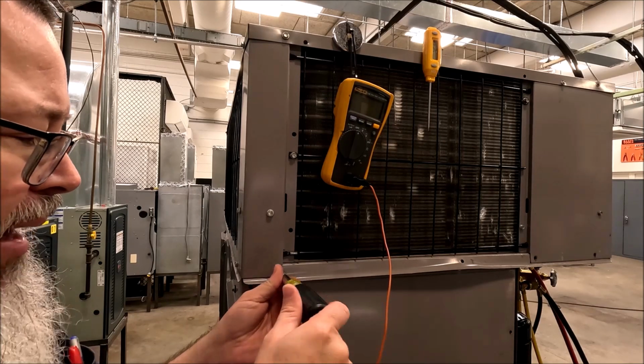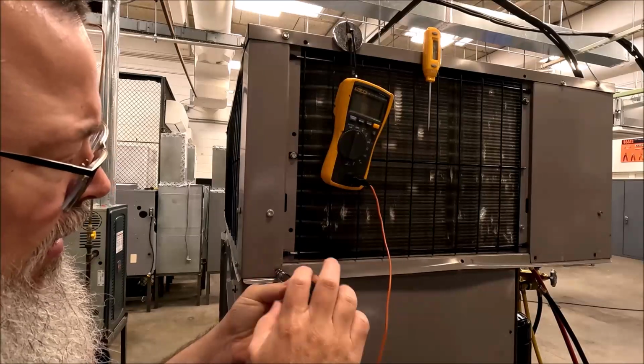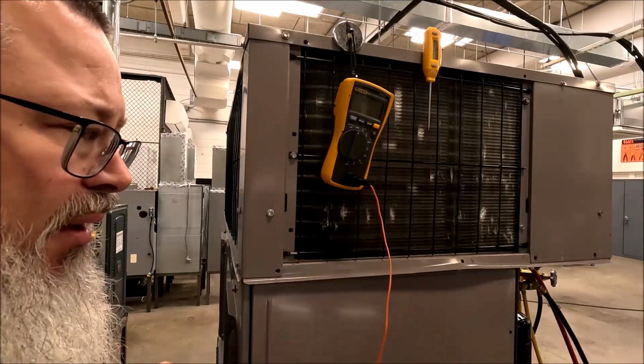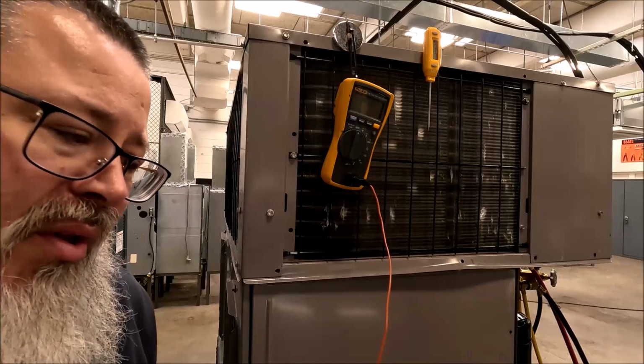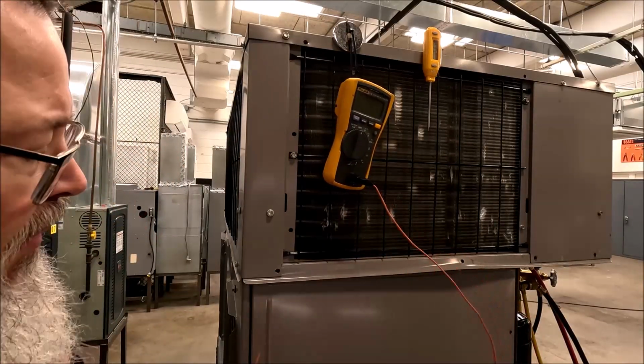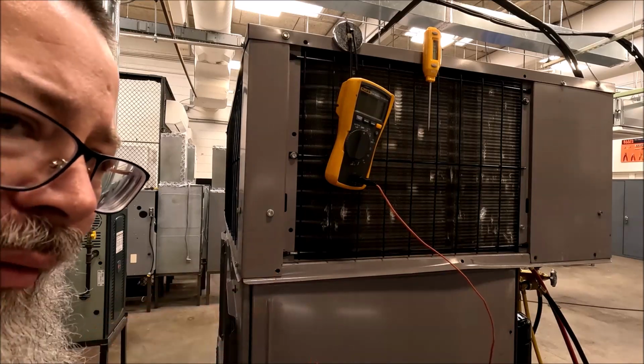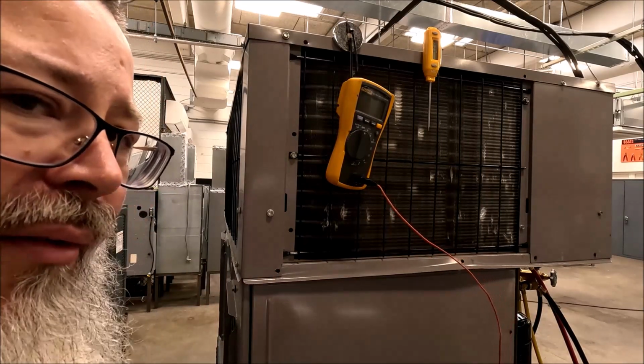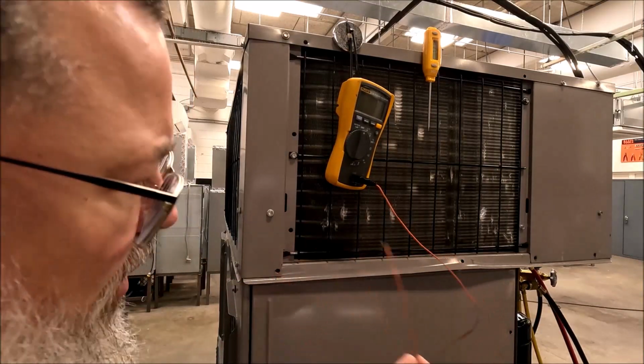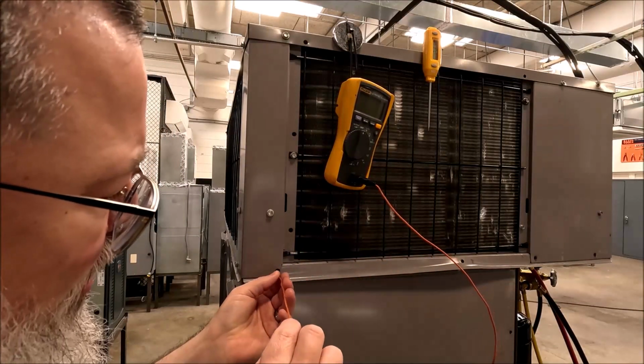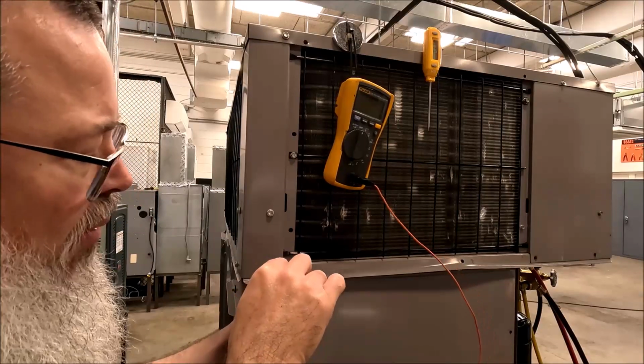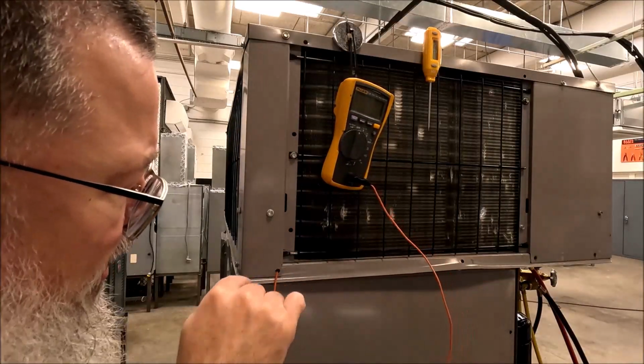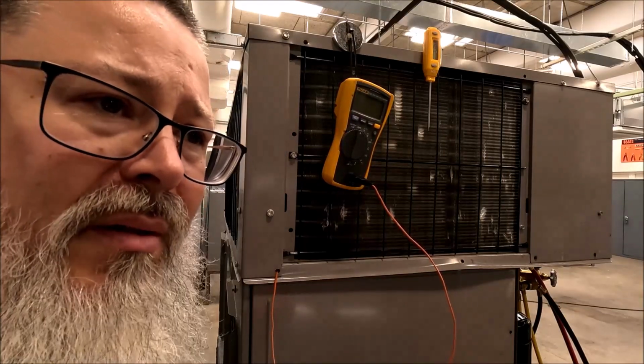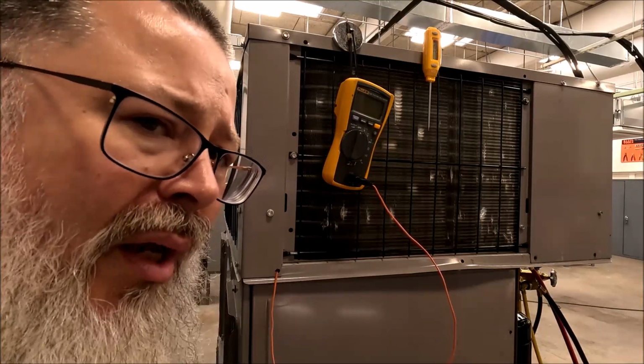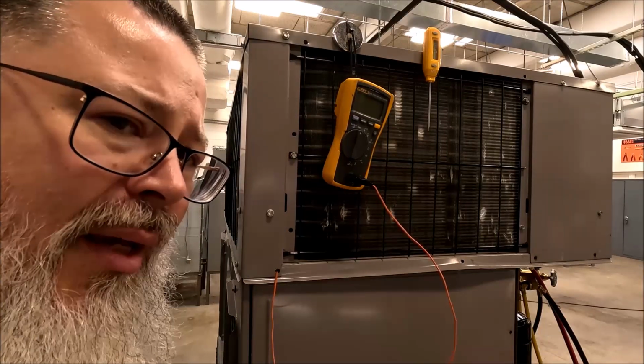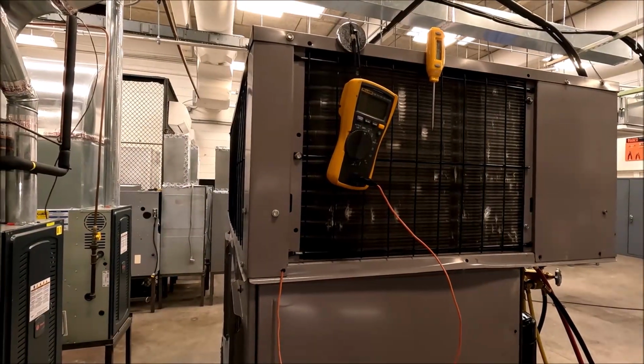And then what I would do is take one screw out. I've seen guys drill holes in the side here and use that for an air temperature port. But usually if you take a screw out, and I've got the luxury of not having ductwork and having this thing on wheels, you can take the little K-type temperature wire that comes with your meter and stick it through that hole. Now if you feel resistance, it's probably the insulation on the inside, so don't push that out. But if it keeps feeding in, okay, and here's the other side, right?